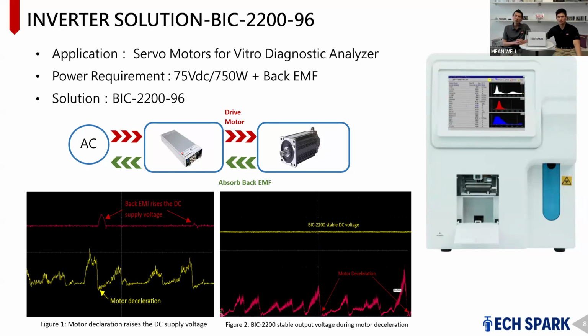Yeah. So we all know the BIC 2200 is very popular in the battery industry, battery testing, where it can be used to charge the battery and then discharge the battery, feeding the battery energy back to the grid in inverting mode. So for this project, the customer was testing one of our AC to DC power supplies, and in the middle of the test, they found out that when the motor was on, the unit went into overvolt protection. And we found out that it's due to the back EMF of the motor when it's braking. The power supply went to OVP.